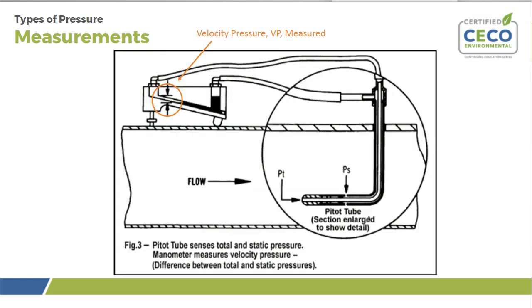A pitot tube is used to measure this and is a tube inside of a tube. And the static pressure is measured in the annulus with the holes on the side of the tube perpendicular to the flow. We can see where the P sub S arrow is pointed downwards. The total pressure is sensed by the air being blown into the inner tube. Velocity pressure, which is the total pressure minus the static pressure, is measured on the pressure gauge, which is the manometer. Velocity pressure is always positive, and velocity pressure will increase as the velocity of air in a duct increases.